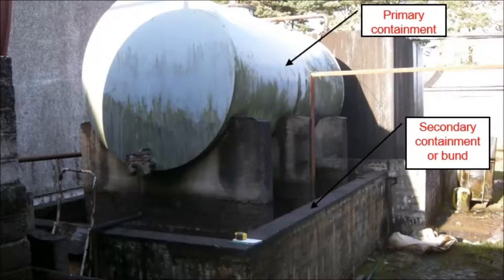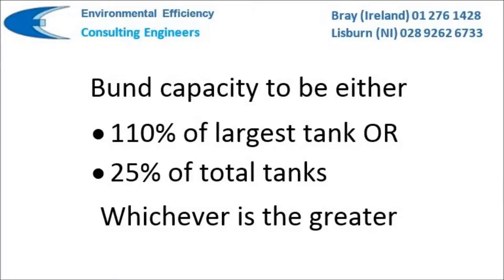The purpose of a bund is to provide secondary containment should the primary containment fail. The first consideration when designing a bund is to decide what the capacity of the secondary containment should be. The general rule in the UK and Ireland is that the bund capacity should be 110% of the largest tank or 25% of the total tank capacity, whichever is the greater. This rule can cause some confusion, so we will explain this with some examples.